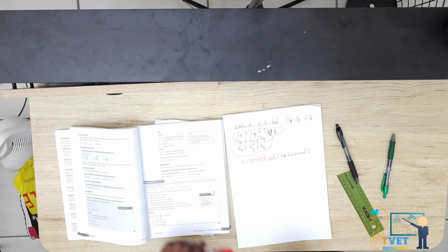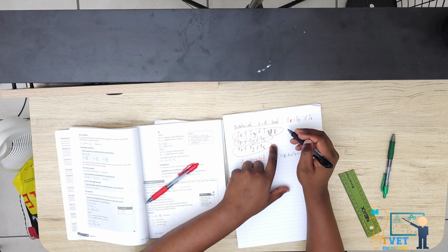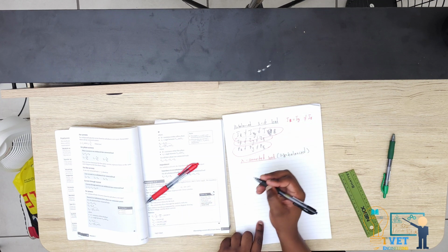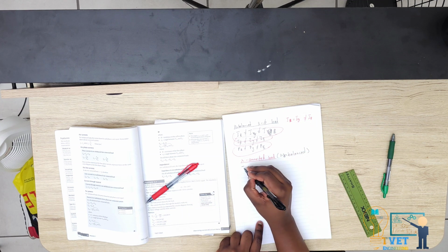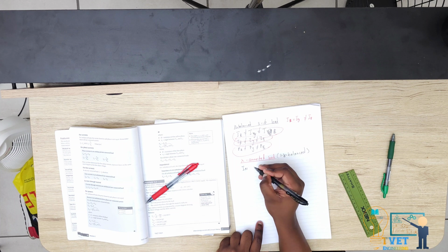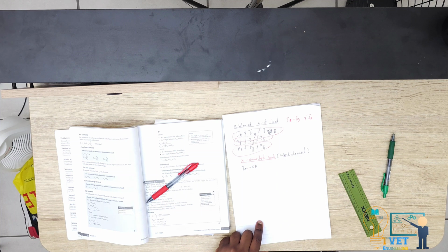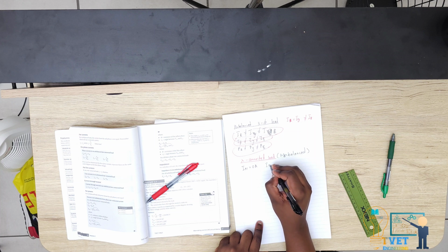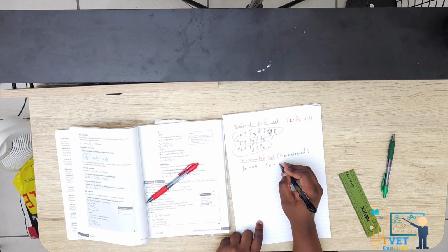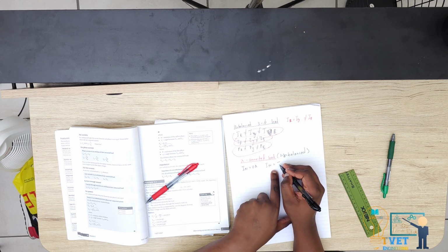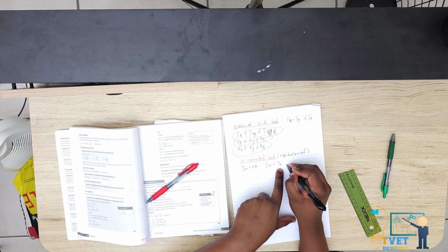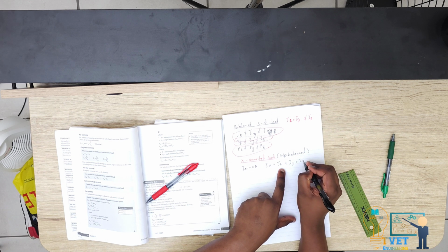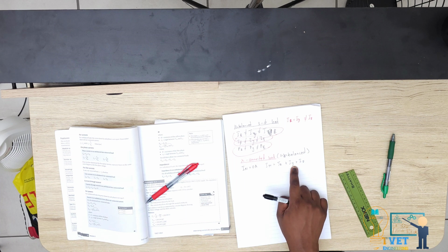And also I forgot to mention, when it is balanced, the current flowing in the neutral is equal to 0 amps. The current flowing in the neutral, we add the sum of these currents. How do we calculate the current flowing in the neutral? IR, the current of the red phase, plus IY plus IB. So you add all the currents to calculate the current in the neutral wire.